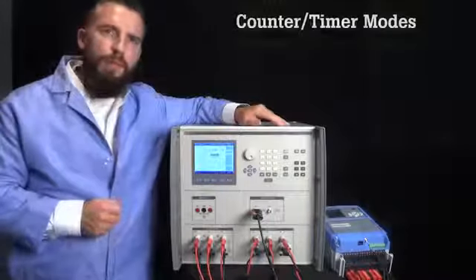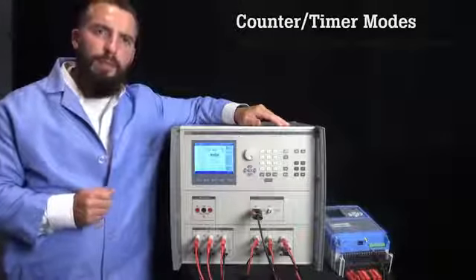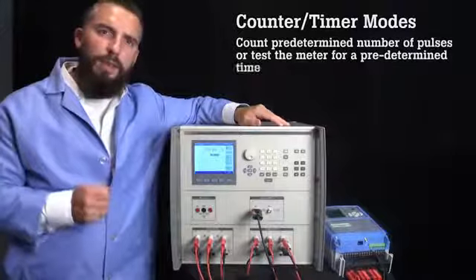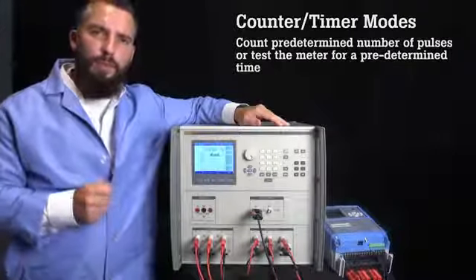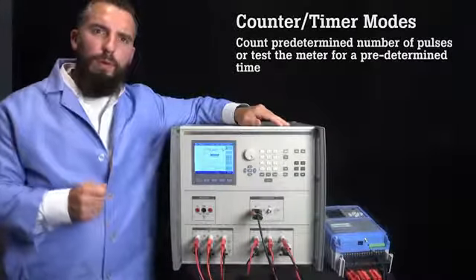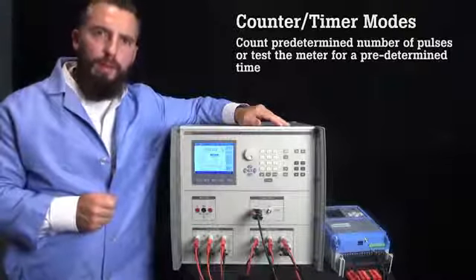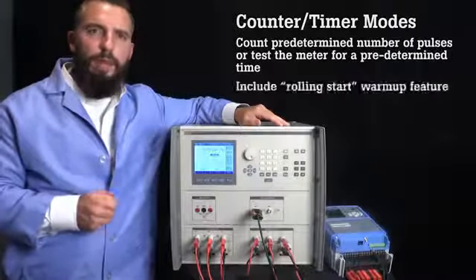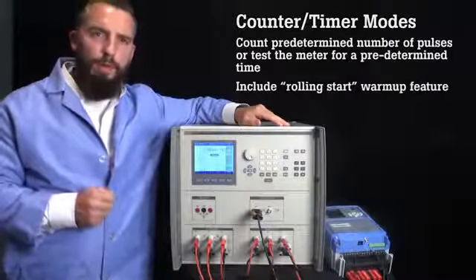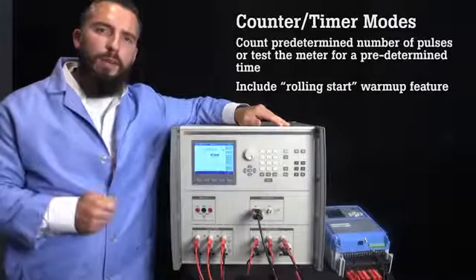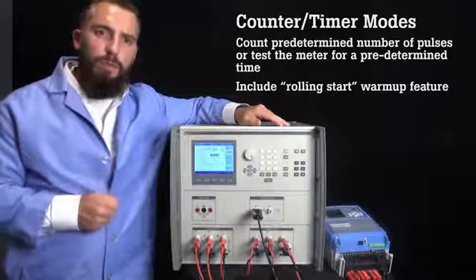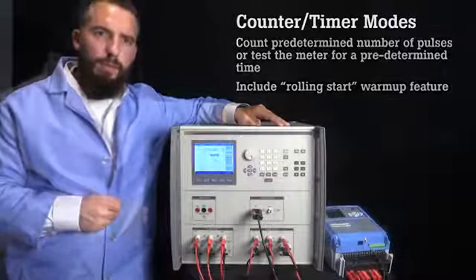The reason counter and timer modes are more repeatable methods to test energy meters is that they either count a predetermined number of pulses from the meter under test, or they test the meter for a predetermined amount of time. Both the counter and timer modes have a warm-up feature for the UUT. This counter method is also known as rolling start method because of the warm-up feature.